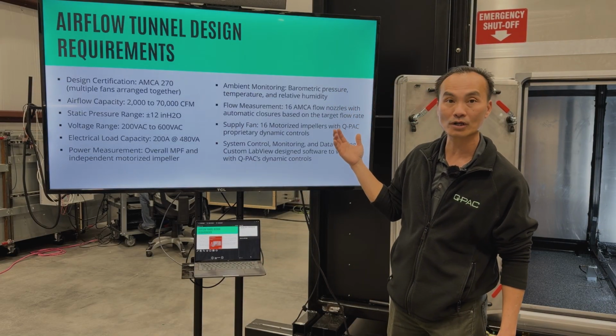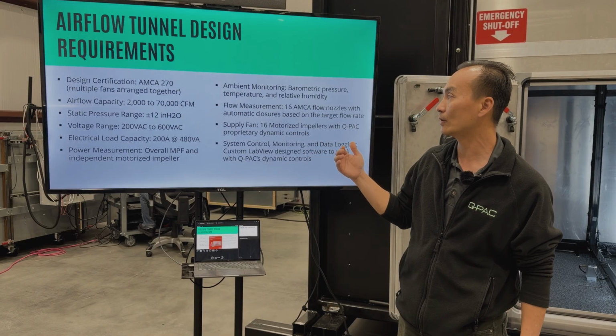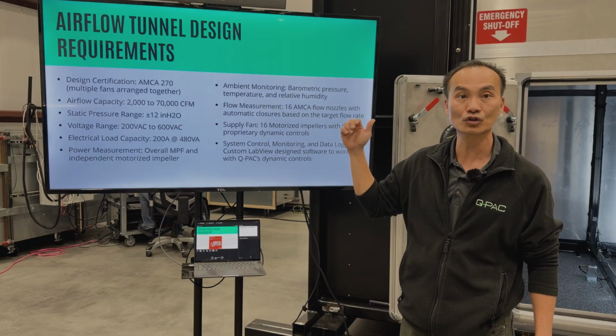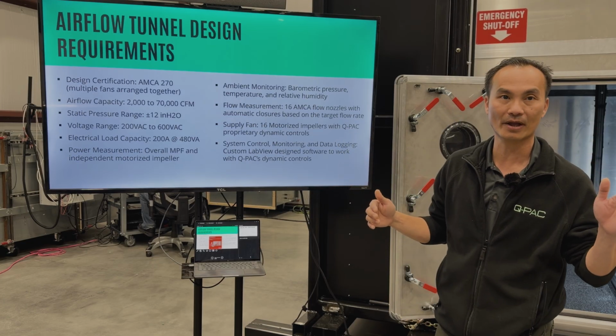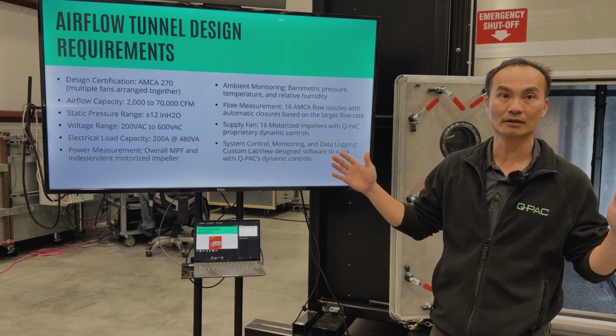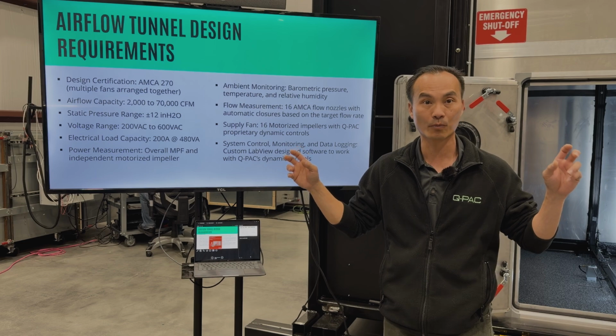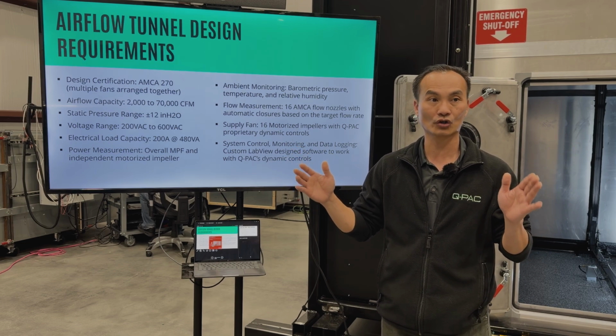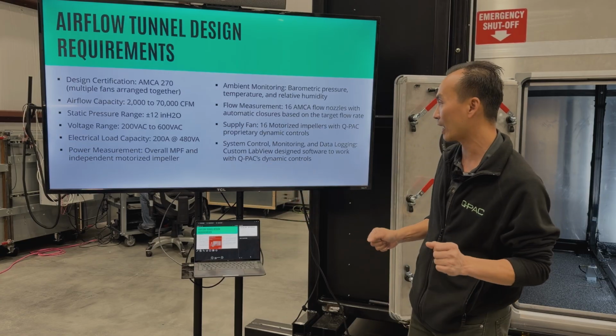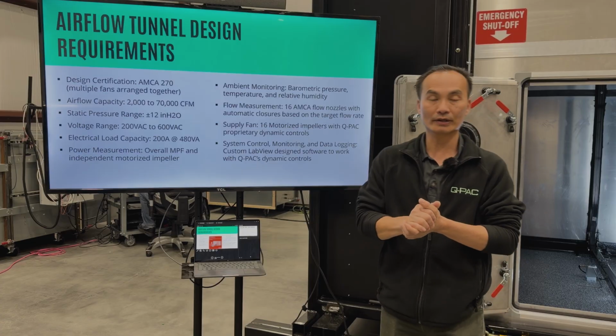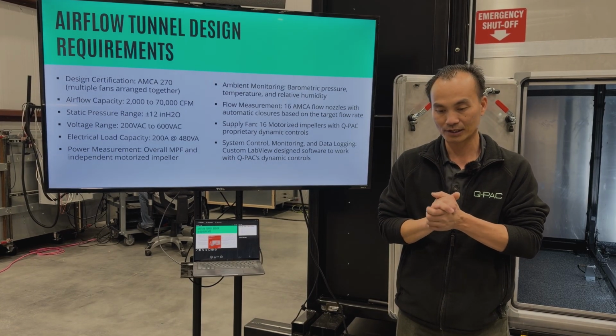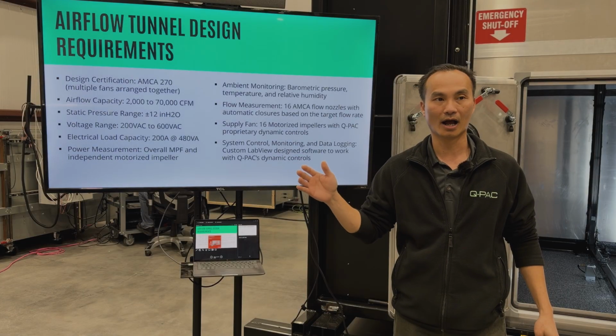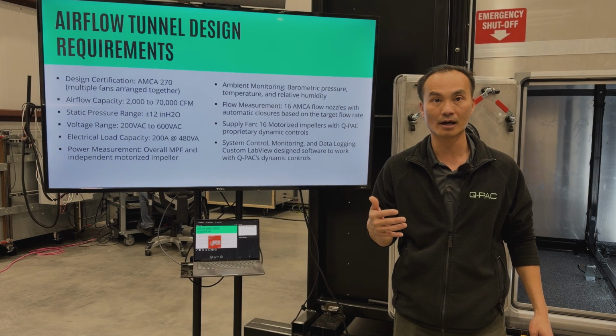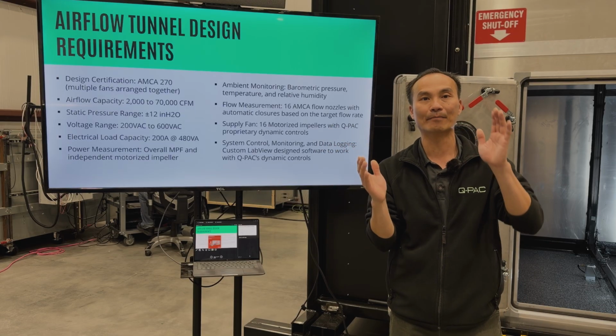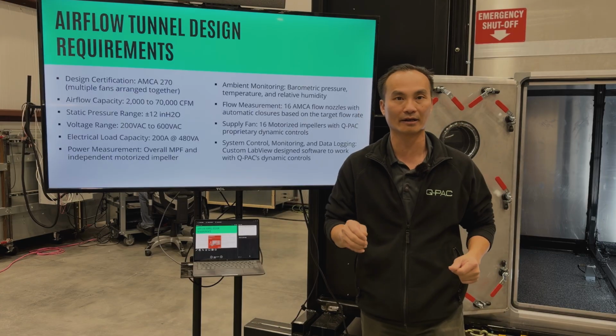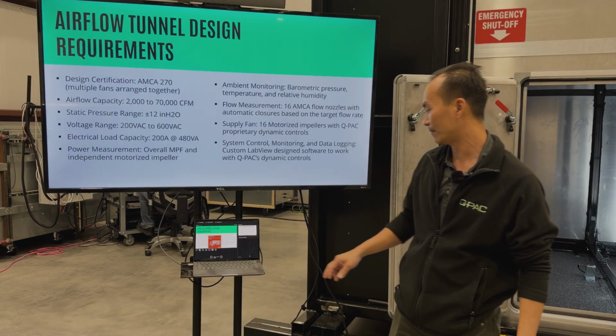Okay. Again, this airflow tunnel is an AMCA 270 airflow tunnel. The capacity of this airflow tunnel can run from 2,000 CFM up until 70,000 CFM. So it's a wide range of operation because we have a wide range of operation on our products. We want to make sure that we can cover and test all the range that we apply to. Why did we stop at 70,000? Good question. 70,000 CFM is not the biggest airflow that we produce on our product, but that's enough for us to test all the dynamic effect if we lay it out a certain way. And I will explain a little bit deeper as we go into this presentation.